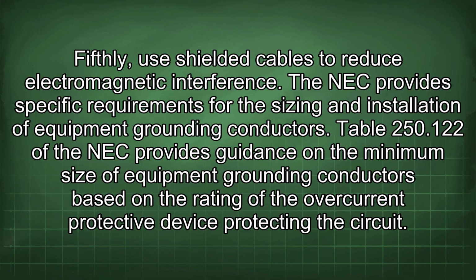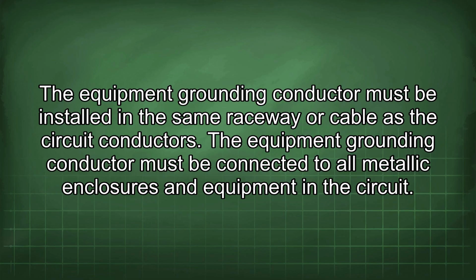The NEC provides specific requirements for the sizing and installation of equipment grounding conductors. Table 250.122 of the NEC provides guidance on the minimum size of equipment grounding conductors based on the rating of the overcurrent protective device protecting the circuit. The equipment grounding conductor must be installed in the same raceway or cable as the circuit conductors. The equipment grounding conductor must be connected to all metallic enclosures and equipment in the circuit.